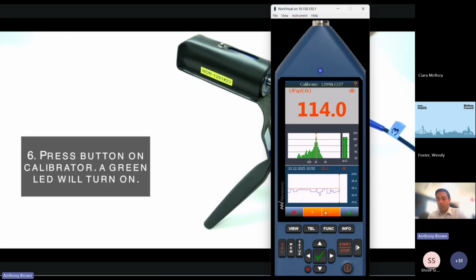Generally, you tend to find that it always reads near enough 114. So you only need to press this plus or minus button once or twice. So it's probably easier doing it in the manual way because you've got the nice big screen. And then there's a sensitivity at the bottom in orange in small text. That should read around minus 25, minus 26, minus 27 maybe. All meters are different. As long as it's around that sort of number, then it should be fine.